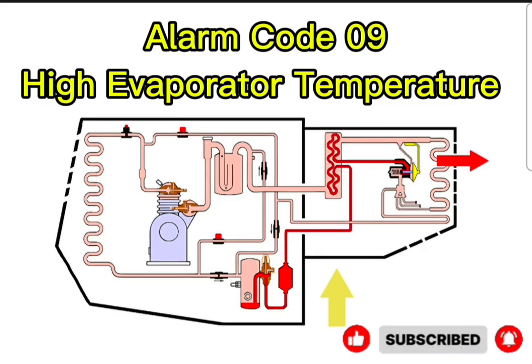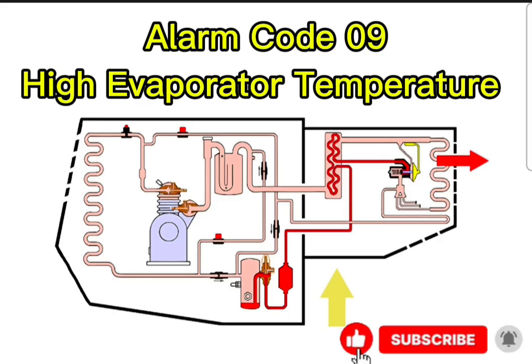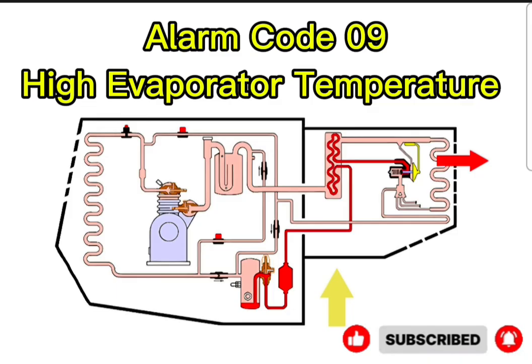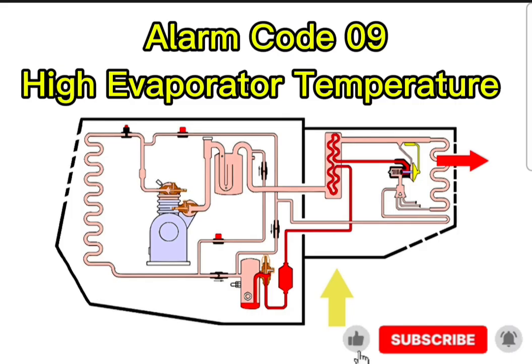Precisely. But the manual adds a detail that completely threw me. It says this specific sensor is an ungraded sensor that does not require calibration. Oh, yeah. I have to push back on that design choice. We are talking about a commercial transport unit that probably costs upwards of $50,000, carrying maybe $100,000 of sensitive cargo. High stakes. If this single sensor has the power to paralyze the entire operation, shouldn't it be the most precise, finely tuned, highly calibrated piece of technology on the board?